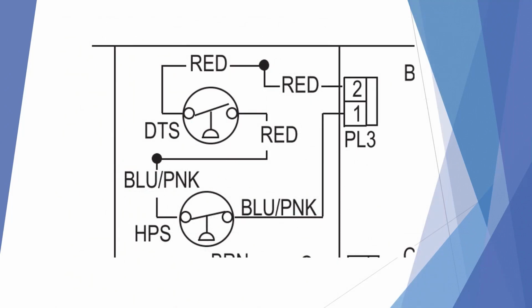Another tip, when you're troubleshooting safety devices on a furnace or, for that matter, any heat pump or air conditioner. Normally, you will check across the safety device to make sure that it's either open or closed, whatever state it's supposed to be in. But many times we have techs tell us they have checked the switch and it's closed, but the furnace or the heat pump is still not running. Usually we direct the technician to jumper that safety circuit at the board where the circuit goes into the board. What this will do is eliminate the wiring and any plugs that are in that circuit. The switch itself may be closed, but the circuit may be open due to a broken wire or a pin in a plug that's not making contact.